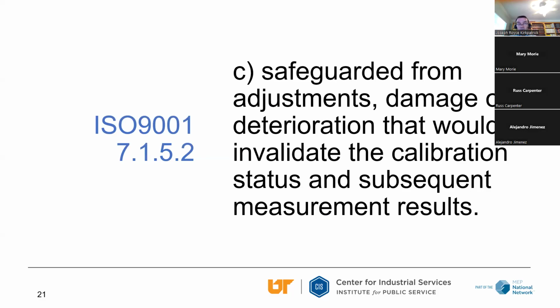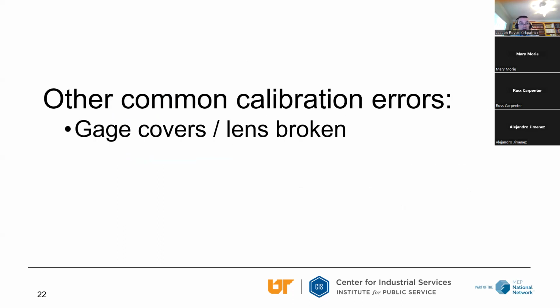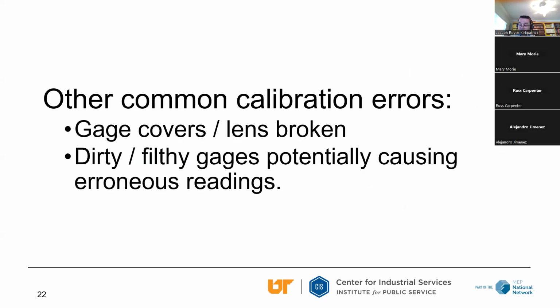Gauges and calibration equipment need to be safeguarded, protected from damage or deterioration that would invalidate the measurement results. Common errors in this are gauge covers being broken, or the lenses being broken, or the gauges being filthy and not protected or not in the right environment, causing potentially erroneous readings. And really, anytime you have a calibration finding, there's a high risk that it could be classified as a major nonconformance in your audit, if, in the opinion of the auditor, that calibration could potentially result in non-conforming product being shipped to the customer.